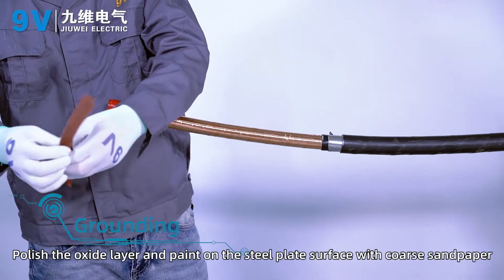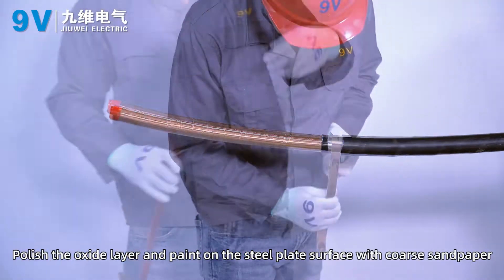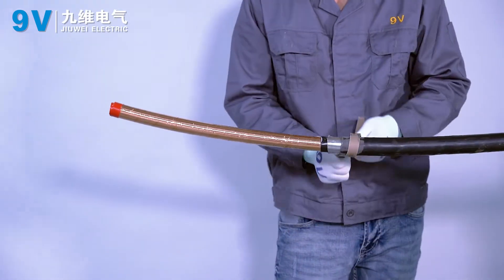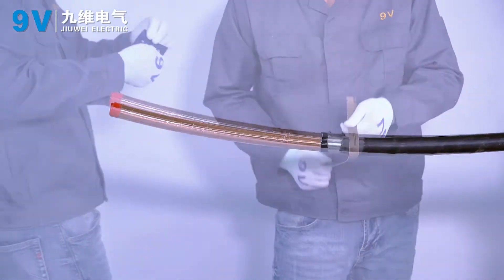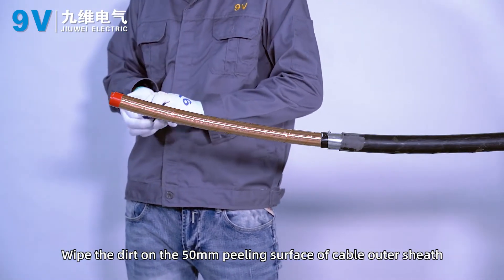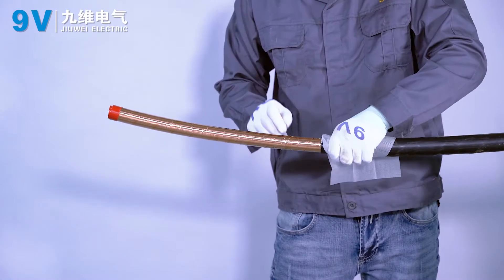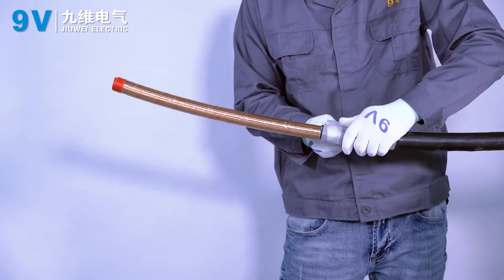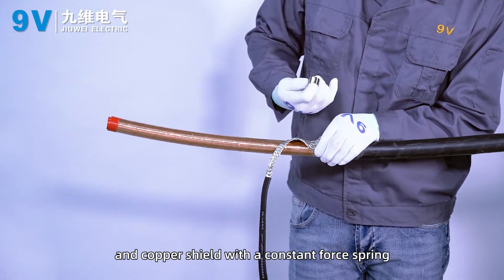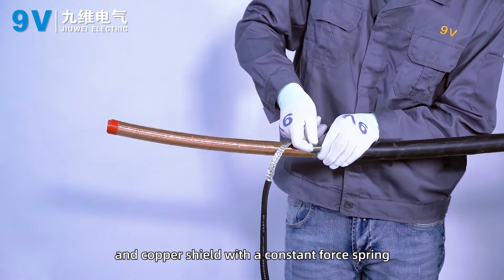Grounding. Polish the oxide layer and paint on the steel plate surface with coarse sandpaper. Wipe the dirt on the 50 mm peeling surface of the cable outer sheath. Fix the grounding wire to the steel plate and copper shield with the constant force spring.